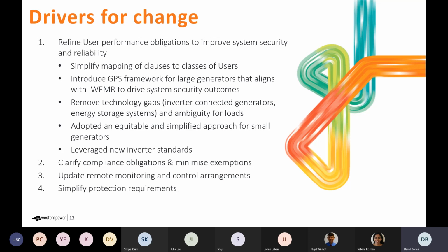And the last thing we wanted to do was to see if we could simplify the drafting of the technical requirements for LV connected inverter-based systems by leveraging the new inverter standard AS4777. And we've largely been able to do that. That leads to simplified drafting in the technical rules, and it also reduces the risk that the technical rules could be interpreted as conflicting or contradictory compared to the Australian standards. That makes it easier for users. It means that they simply need to comply with the Australian standard.